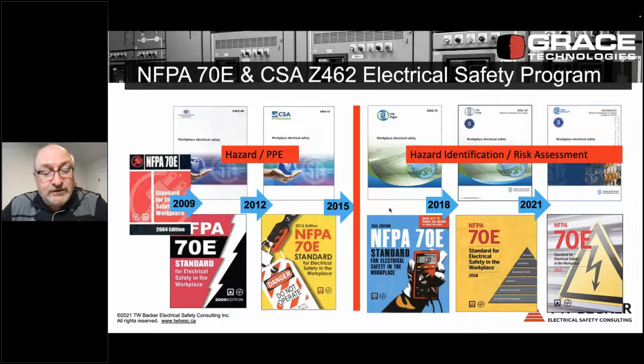The employer needs an overarching job-based risk assessment procedure, and underneath it, the expectation is to define additional protective measures. The qualified person completes a shock risk assessment and an arc flash risk assessment. So there's a lot more detail now that you need to be aware of specific to the requirement for an electrical safety program.